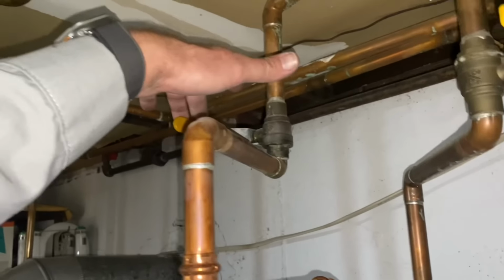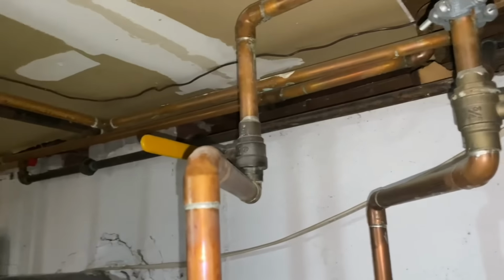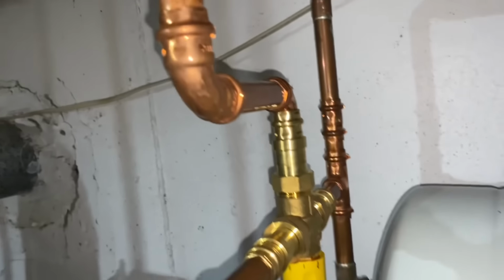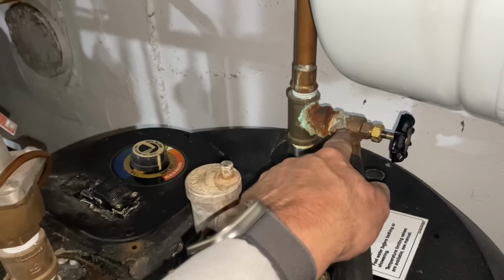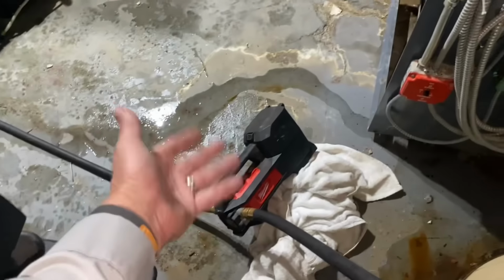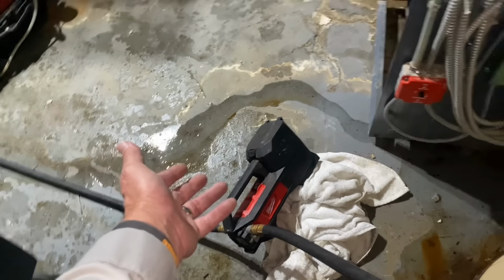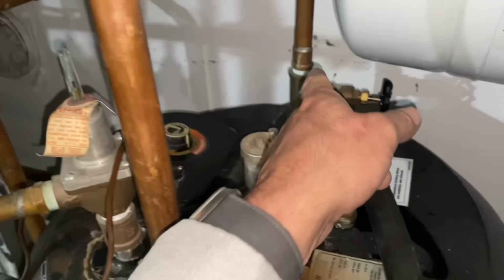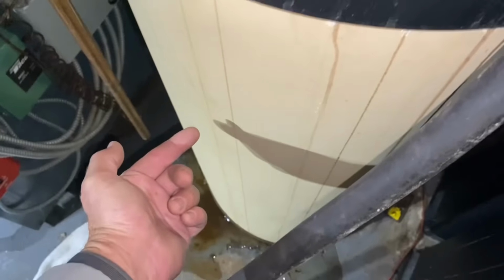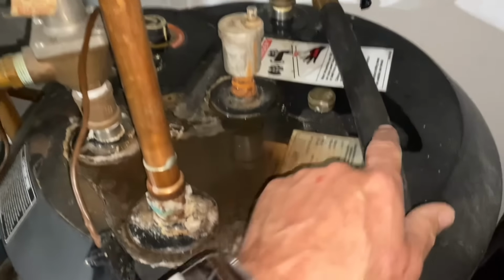All right, I am now draining the domestic side of the tank. It is very important that you have the domestic hot and cold isolated, like I have it right there. We don't want to cut any of this piping right now. Right now, I have this valve open. I started a siphon process, and once I saw it wasn't pumping any more out of the tank, I popped open the relief valve head, right? And now, which means in a dip tube, all of the water from the bottom of the tank is being pumped out through my hose, transfer pump, and then outside.